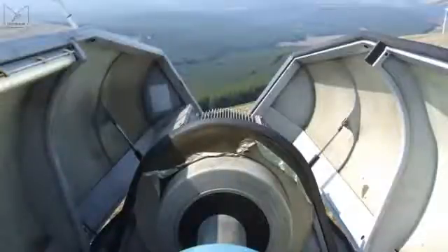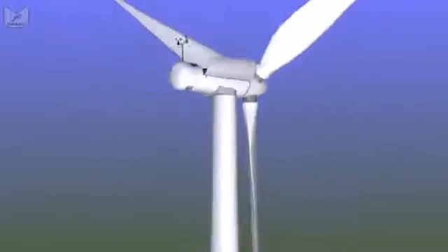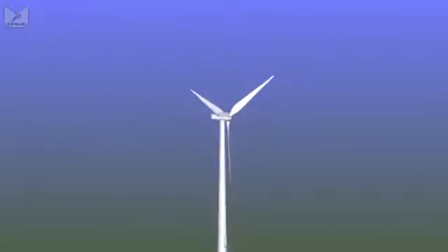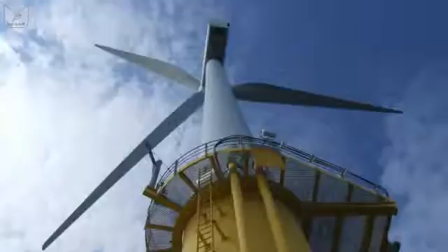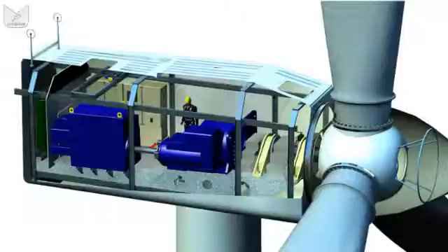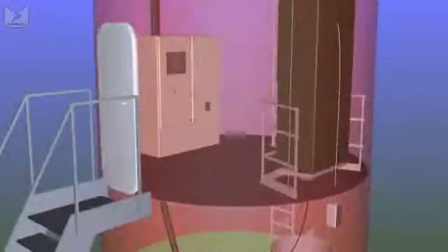The layout of a larger turbine is broadly similar but some components are in different places. Where we place the high voltage transformers in multi-megawatt turbines is a lot more variable. We have a lot more room so we can decide if they can be in the nacelle, at the base of the tower, on platform one, or outside in a hut. In this example the transformer's at the top, so when we go into our door we'll not find a transformer. We do have the high voltage switches in this case on platform two, but on the entrance platform we have the usual control cabinet and a lift.